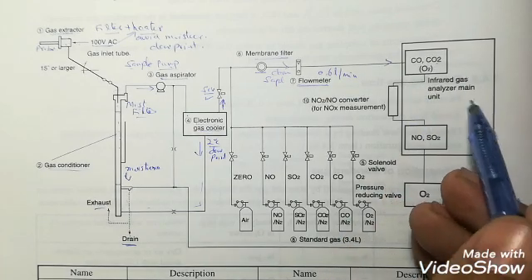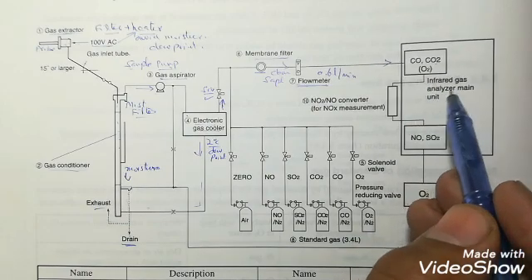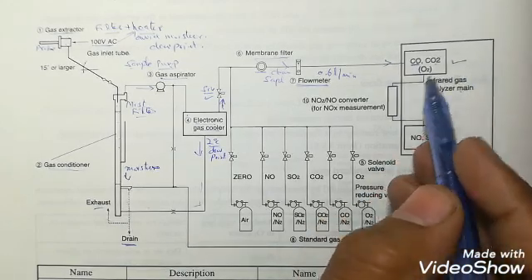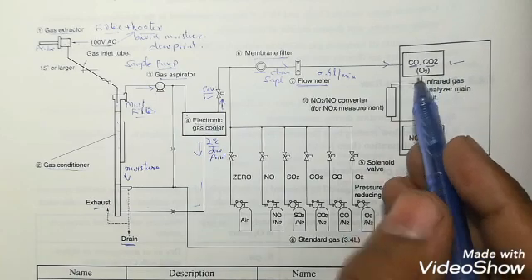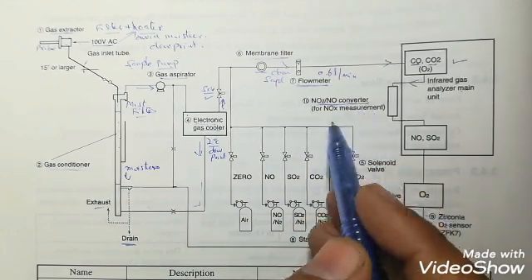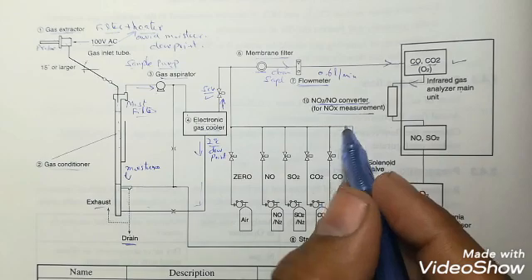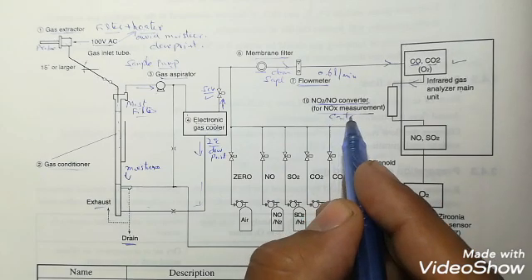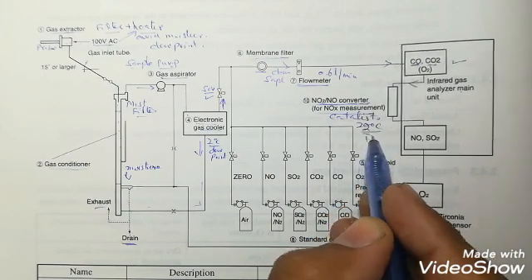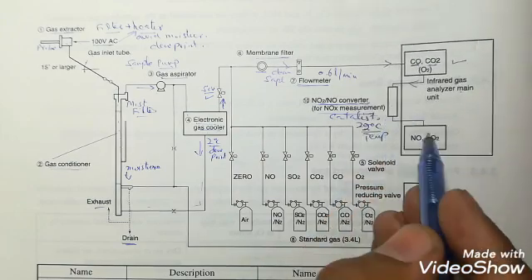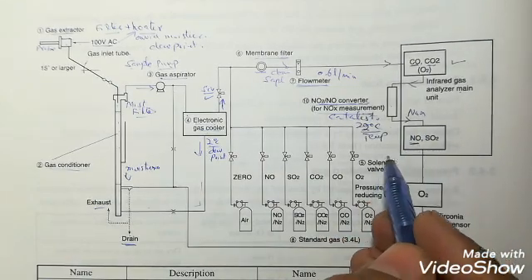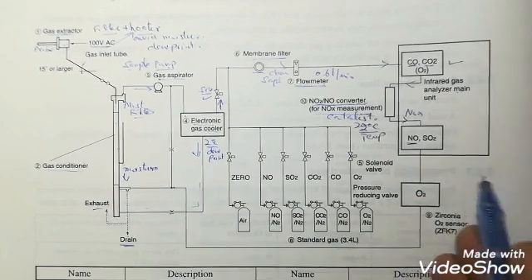Then the gas analyzer, which is a CO or CO2 module, which is an infrared gas analyzer module, this is the main unit. It will measure the CO inside the sample. Then this sample reaches the NO2 to NO converter. This converts the NO2 into NO. Here we maintain the temperature of 220 degrees centigrade. We use a catalyst to convert NO2 into NOx, then NOx is measured in this second module.